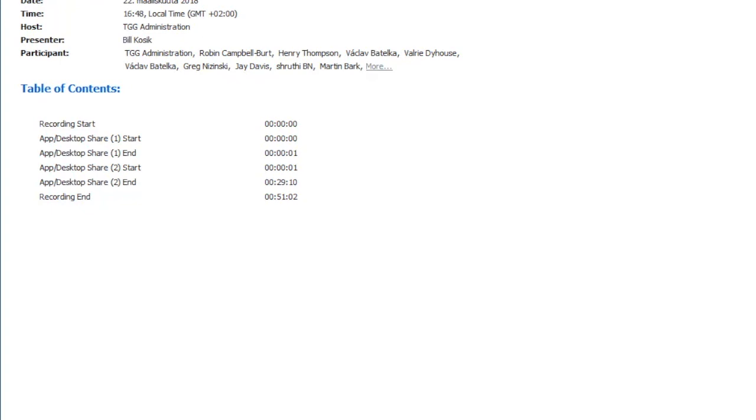Yes, it does. I'm assuming when we go to the high power processors, that would be a liquid cooling case. The way it's done is first start by modeling. You could zero out the water cooled equipment side and run the analysis using just air-cooled equipment at whatever temperature you're running the supply at, and then you can get that TCO, and then go back and basically do the opposite.